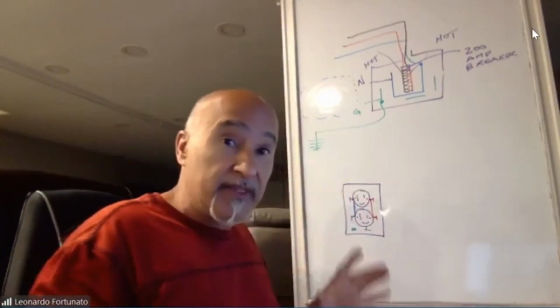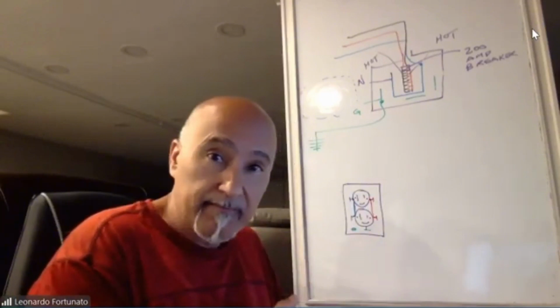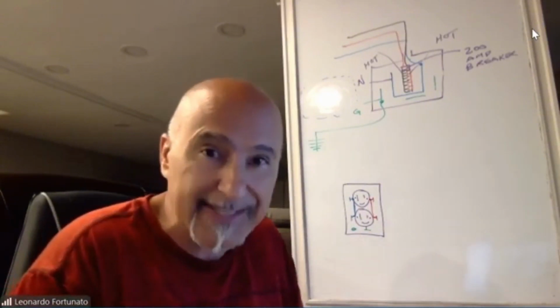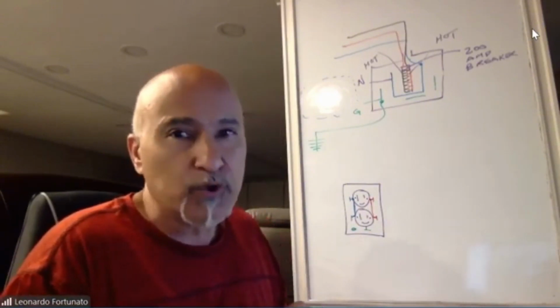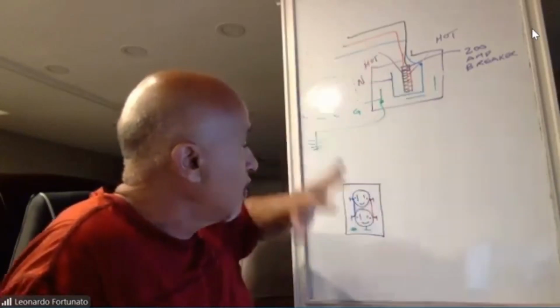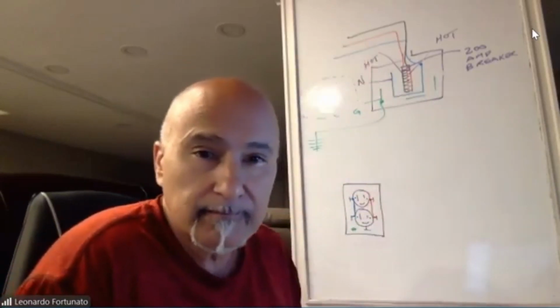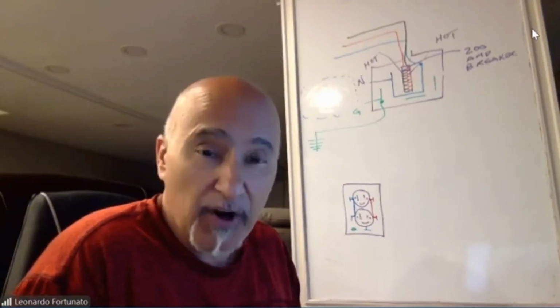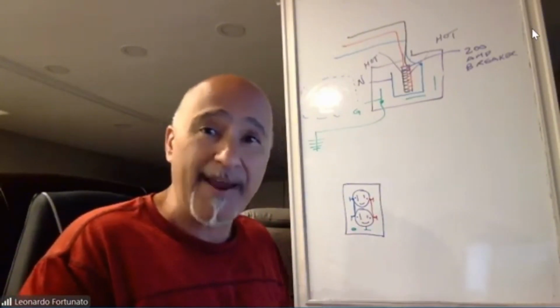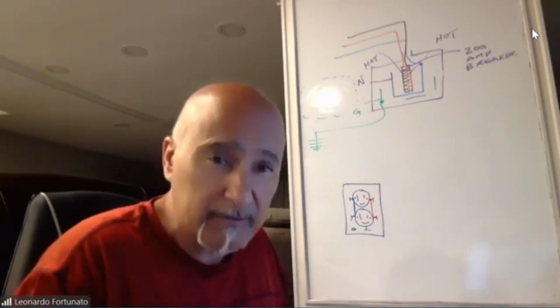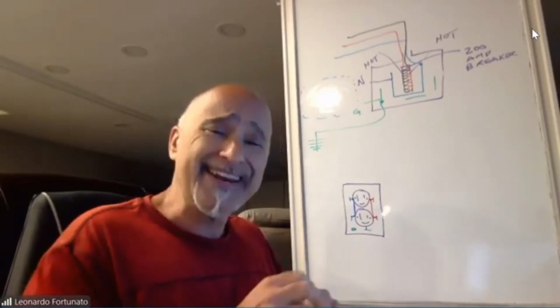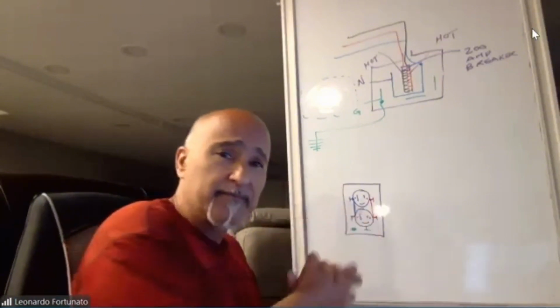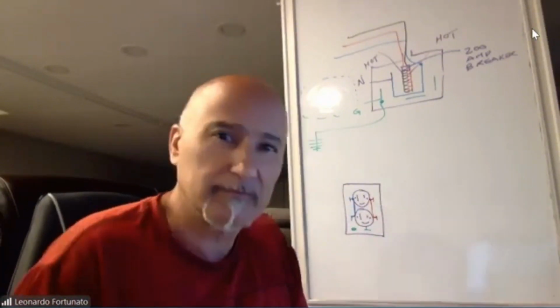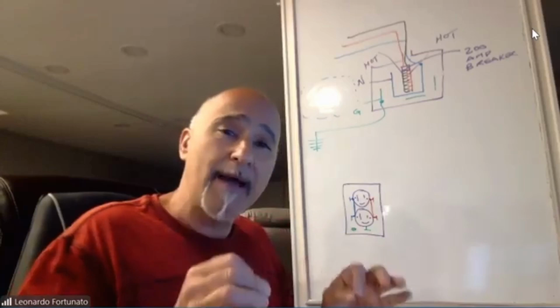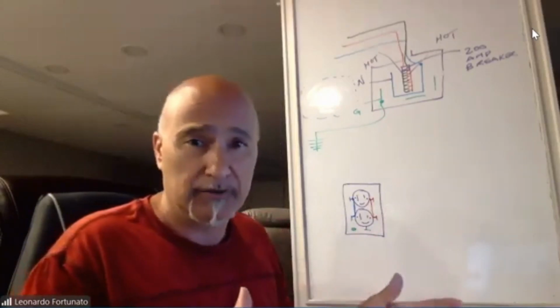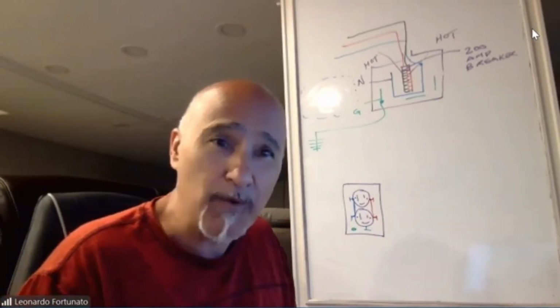Let's connect this. This being a common 15 amp receptacle, can somebody tell me what kind of wire I need to run from my electrical panel to this receptacle? 14—American wire gauge number 14, yes. And how many conductors will I need to connect this receptacle? Two, not counting the ground—so we have two conductors, black and white.